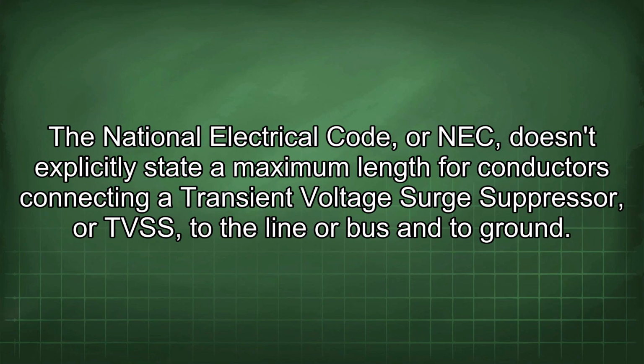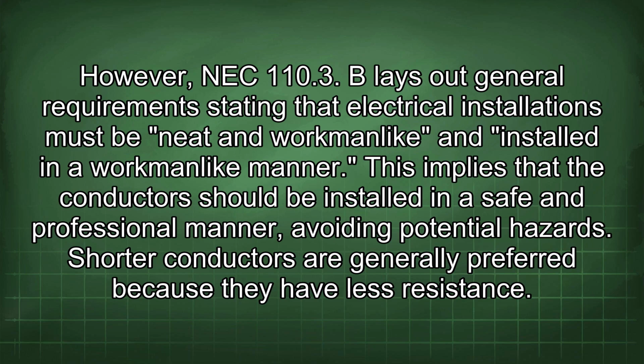The National Electrical Code, or NEC, doesn't explicitly state a maximum length for conductors connecting a transient voltage surge suppressor, or TVSS, to the line or bus and to ground. However, NEC 110.3(B) lays out general requirements stating that electrical installations must be neat and installed in a workmanlike manner. This implies that the conductors should be installed in a safe and professional manner, avoiding potential hazards.